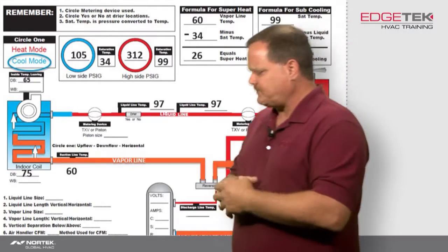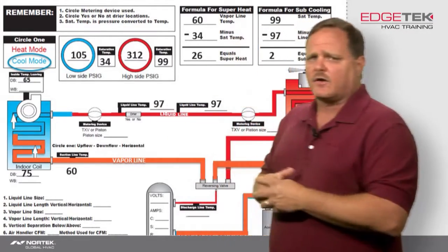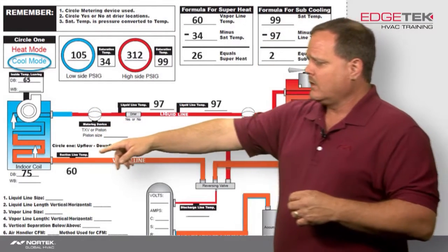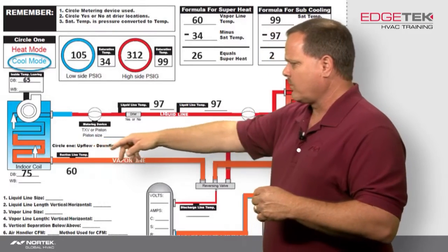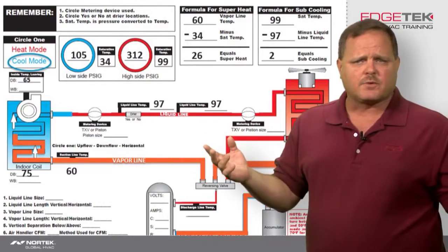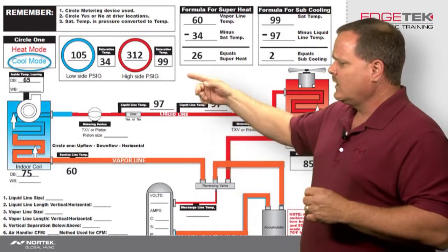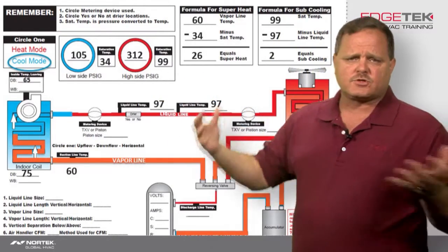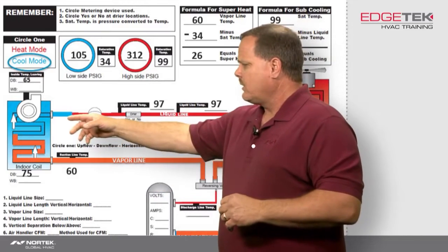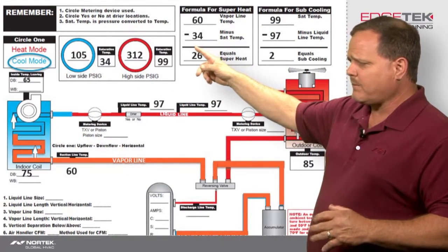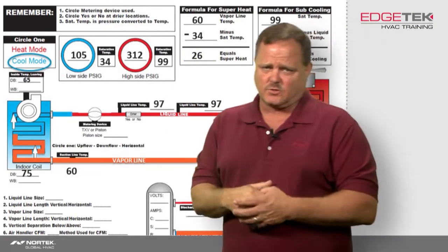We've got an undercharge. So what's happening here? Well, again, our suction pressure is low, but look at our evaporator now. It's warm coming back. That suction line's warm coming back, and we can also see that by the superheat. You can't see it by just looking at it. You have to take some temperature readings. Our 34-degree evaporator temperature is the same as it was with low airflow, but we got a 60-degree suction line temperature minus the 34-degree evaporator temperature, giving me 26 degrees of superheat.